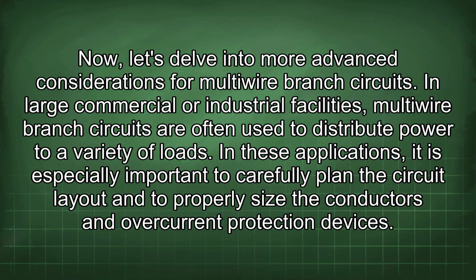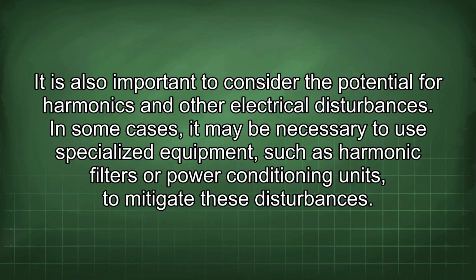Now let's delve into more advanced considerations for multi-wire branch circuits. In large commercial or industrial facilities, multi-wire branch circuits are often used to distribute power to a variety of loads. In these applications, it is especially important to carefully plan the circuit layout and to properly size the conductors and overcurrent protection devices. It is also important to consider the potential for harmonics and other electrical disturbances.